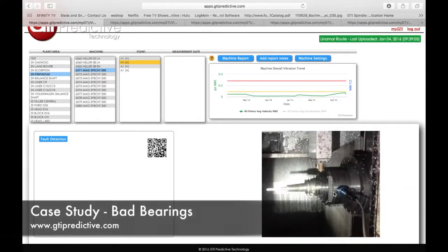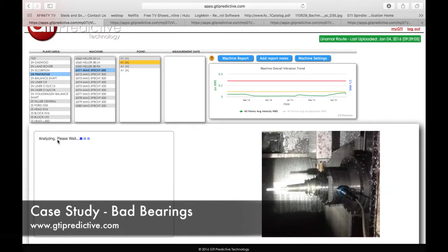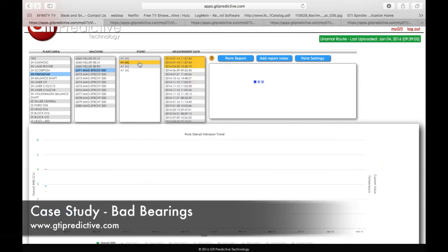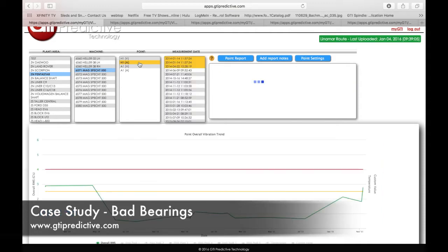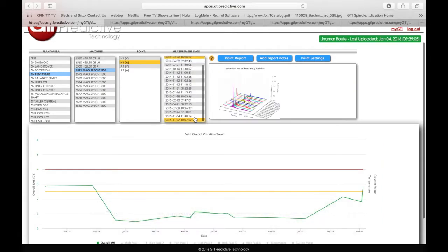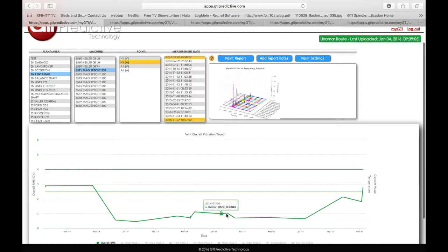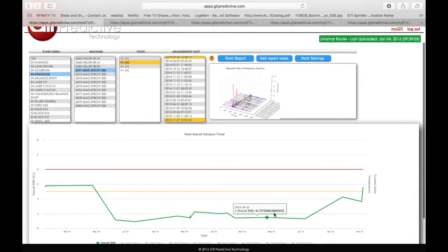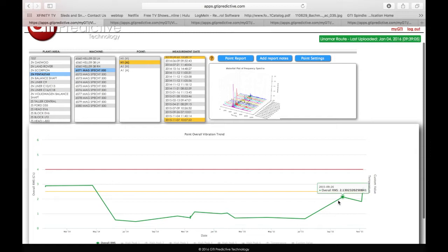We've got another spindle here. We're going to go back to our fault detection, and here it's not saying an imbalance problem at all. It's saying bearings are unsatisfactory. So we go and look at our yellow here, scroll down to our very last read. We can look at our trend as well and see that obviously it was a problem before it was replaced or fixed, and now it's been for months doing well.